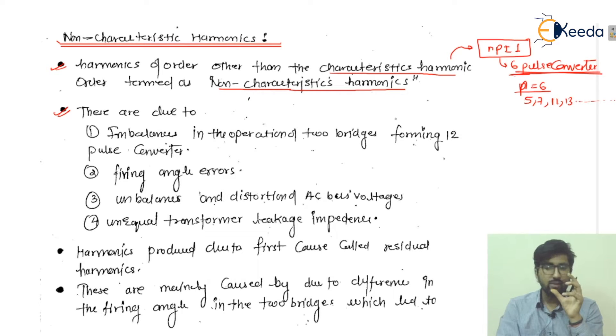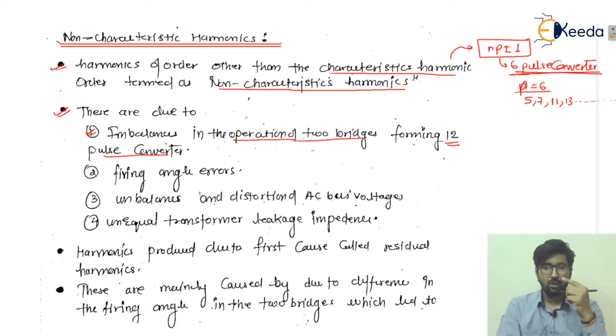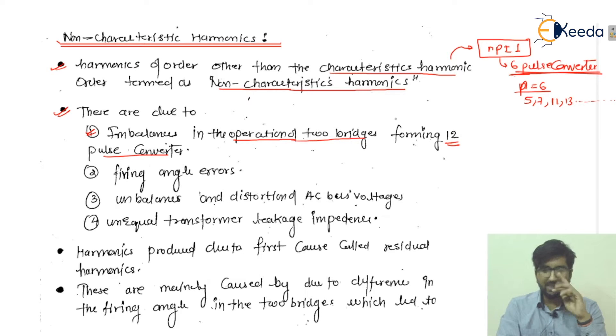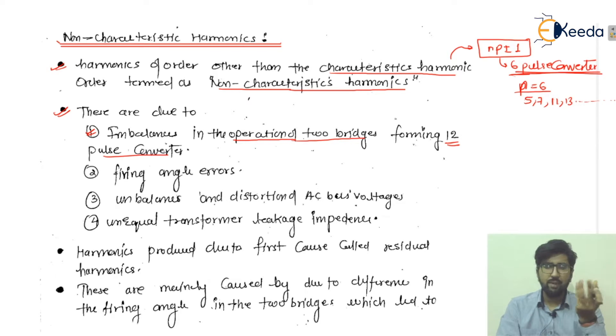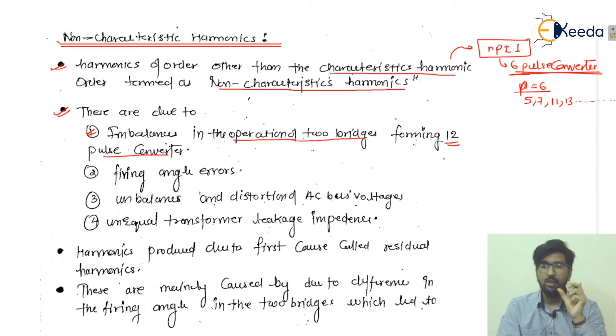The first cause is imbalances in the operation of the two bridges forming a 12-pulse converter. In a 12-pulse converter, we have a six-pulse thyristor bridge on the upper side and another six-pulse converter on the lower side. If there is an imbalance between the two converters — due to current flow, voltage, or delay angle differences — or if there are connection issues, this can give rise to non-characteristic harmonics.